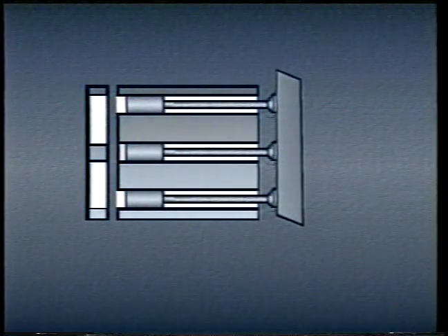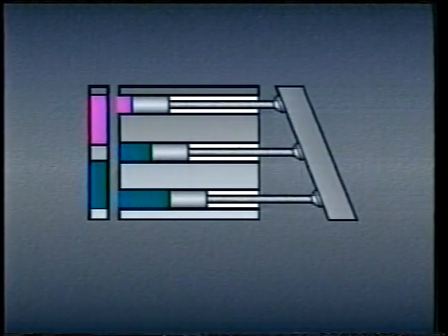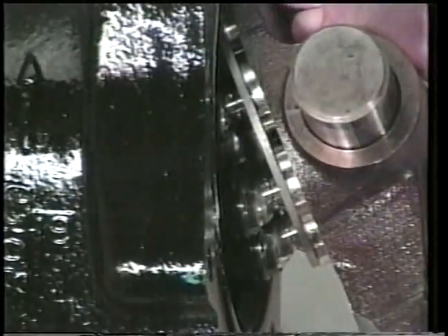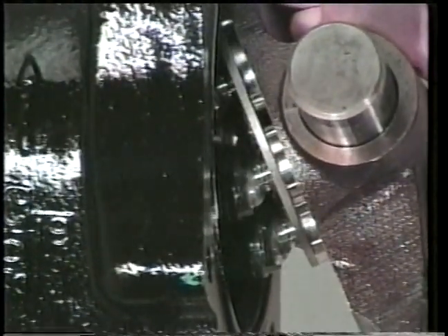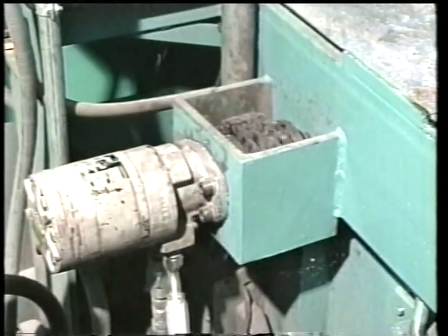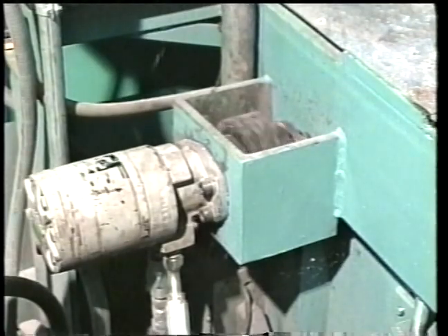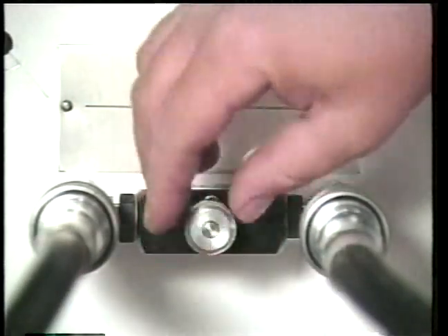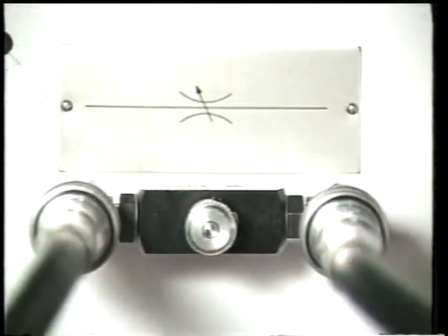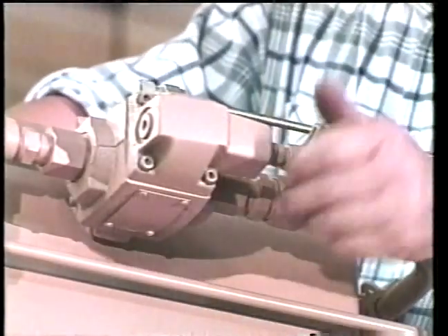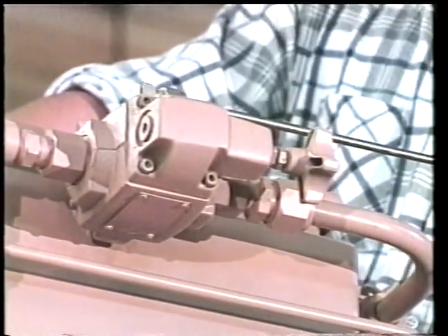When the motor is restarted with the swashplate tilted over center, the piston shoes, which had been rotating in one direction, go back the other way, turning the cylinder barrel in the opposite direction and reversing the direction of the motor shaft. Both speed control and torque control of hydraulic motors is common in industry. Usually, speed is controlled by flow control valves, while torque is controlled by varying the pressure or the displacement.